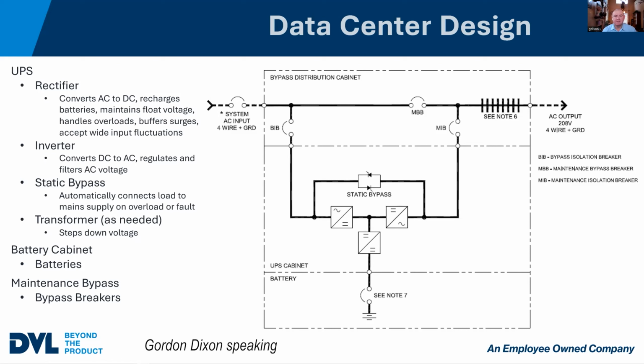The picture on the right shows what we're talking about, the bypass distribution cabinet or maintenance bypass. The power goes through there and it has internal breakers. So if you needed to work on the UPS, change out the batteries, or work on a flywheel, you can turn these breakers off, and that allows the utility power to pass right straight through, giving you the chance to work on those.